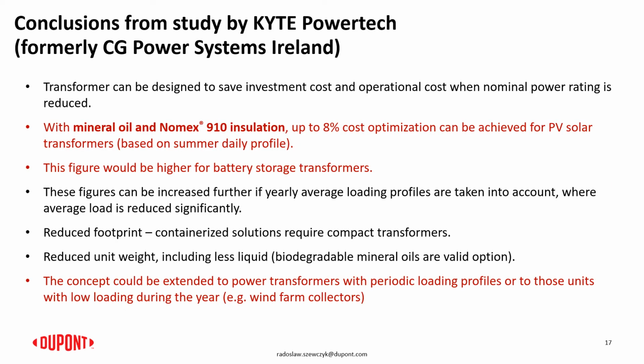The conclusions from the KYTE Powertech study showed that the cost optimization could be at least 8% as compared to the conventional insulation, and for some applications in the energy storage transformers that could be even higher. So that was an important conclusion, that optimization of the transformer design based on the typical observed loading patterns for the photovoltaic transformers or the energy storage installations would be possible, and the alternative insulation systems could be good enablers for cost optimization in such installations.